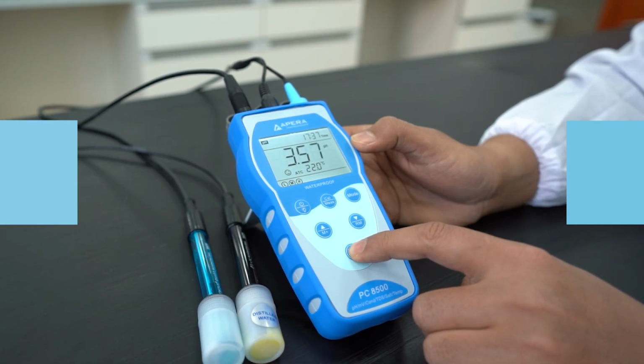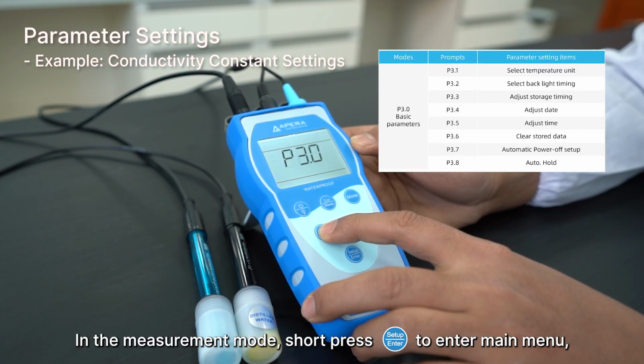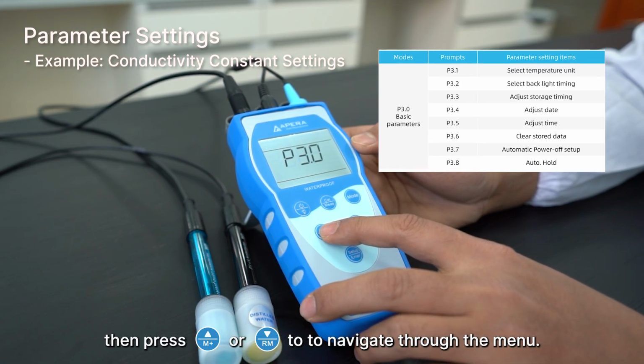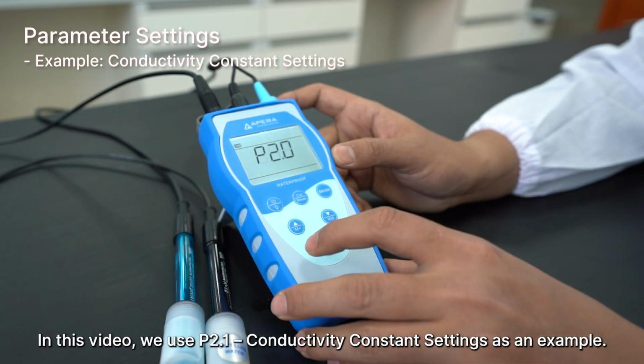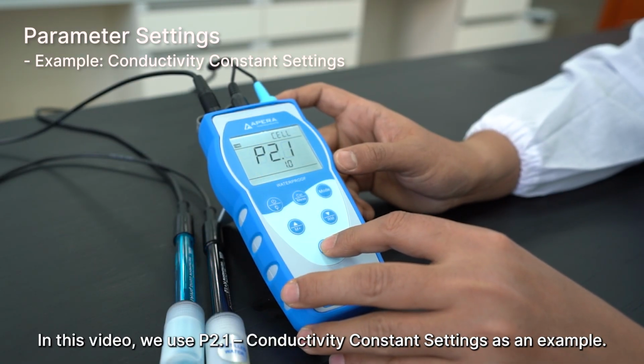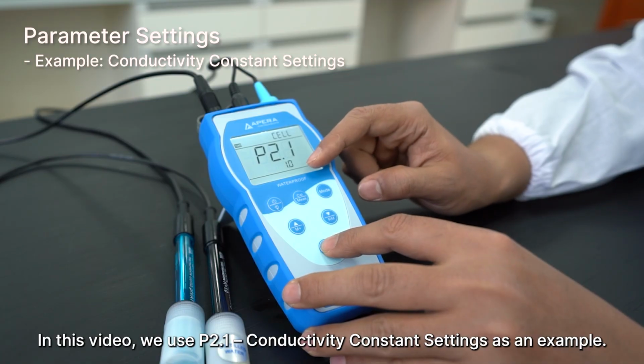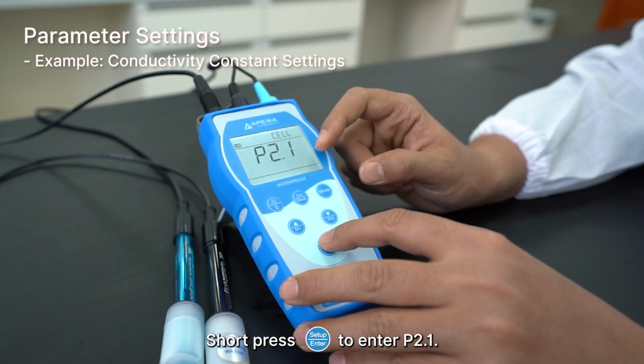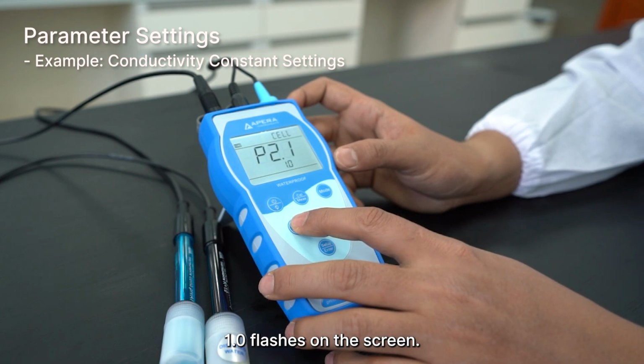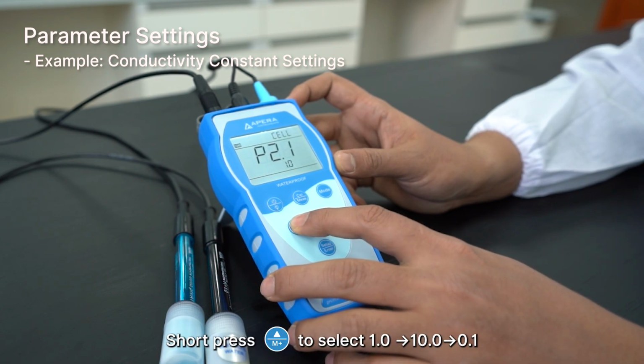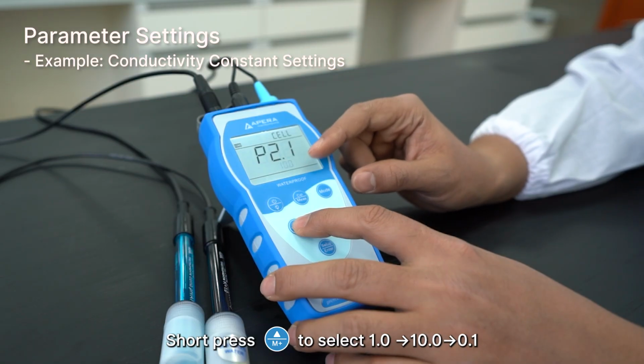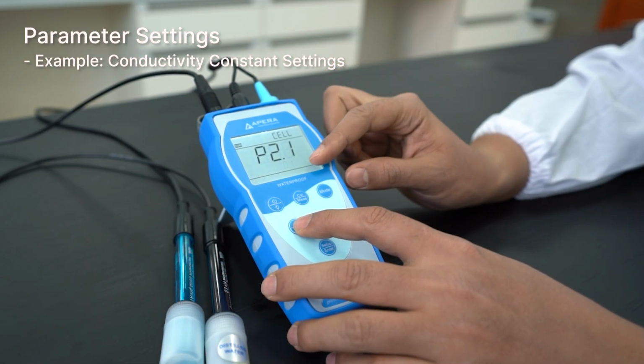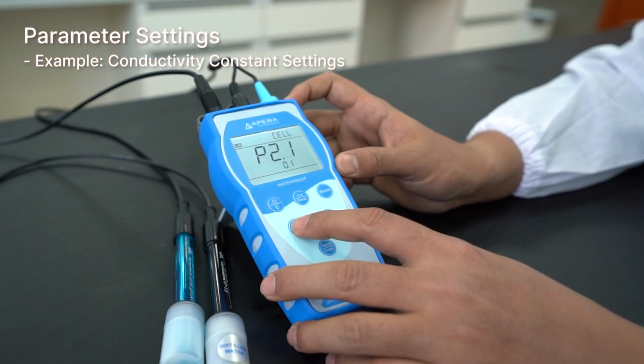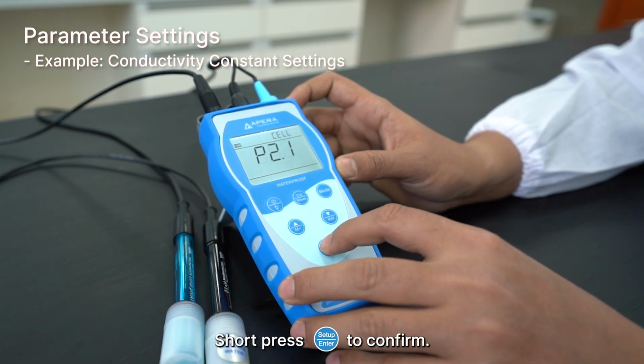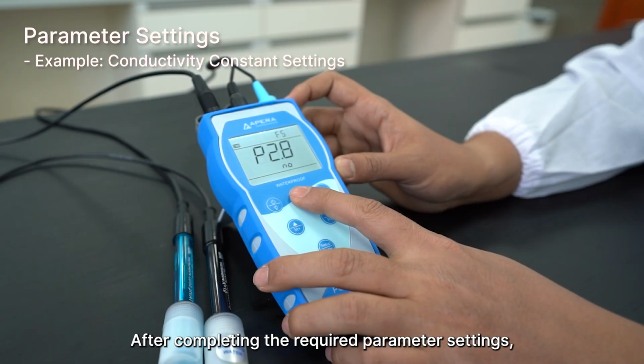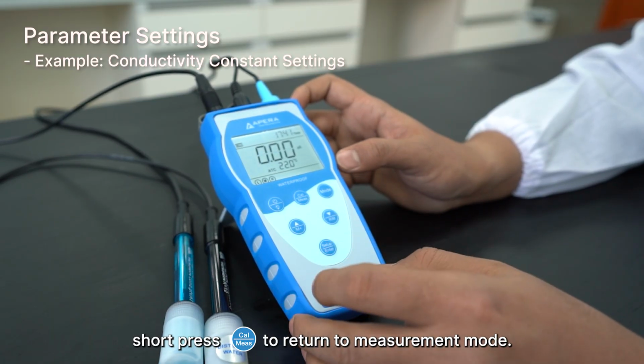Parameter settings. In the measurement mode, short press Setup button to enter main menu, then press up or down to navigate through the menu. In this video, we use P2.1 conductivity constant settings as an example. Short press Enter to enter P2.1. 1.0 flashes on the screen. Short press the up key to select 1.0 to 10.0 to 0.1. Short press Enter to confirm. After completing the required parameter settings, short press Measure button to return to measurement mode.